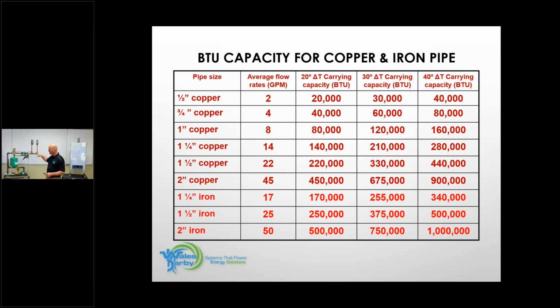Yes, at a 15-degree delta T, a gallon of water has different abilities at a 30. But if I don't have the heat emitters, and that goes back to when I said make sure you remove the cover off the aquastat on that cast iron boiler before you replace it. If I look at baseboard heat at 200 degrees, I may get 600 BTU per foot. If I look at that same exact piece of baseboard per foot at 170 degrees, I may only get 530 BTU per foot. So be cautious here. Changing the delta T is not going to deliver more BTU. A BTU is still a BTU.